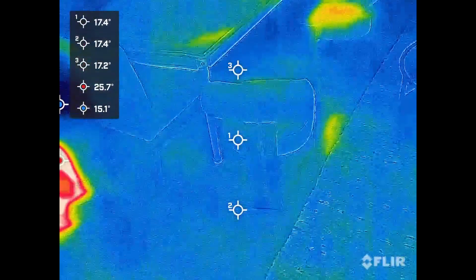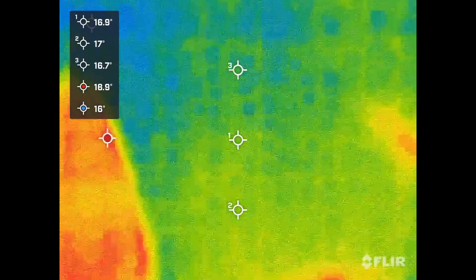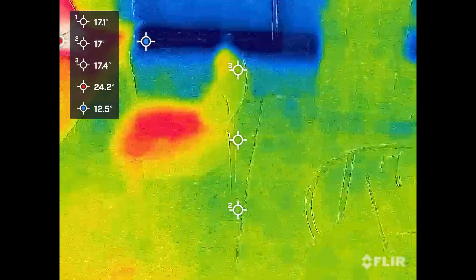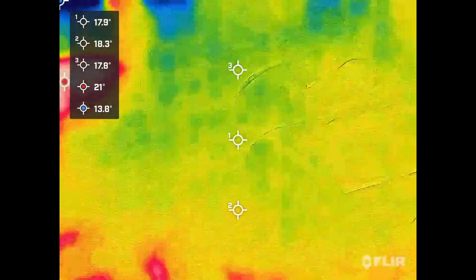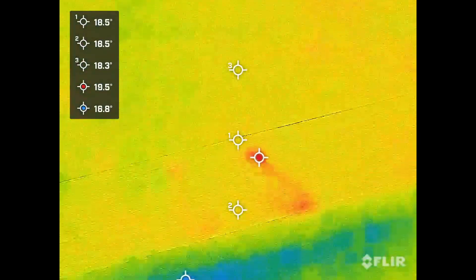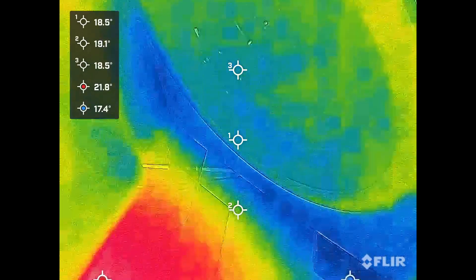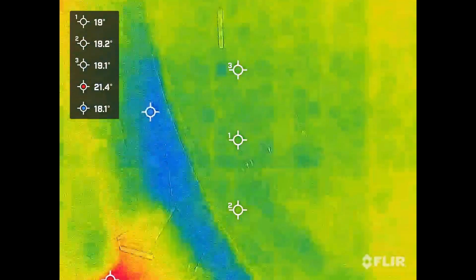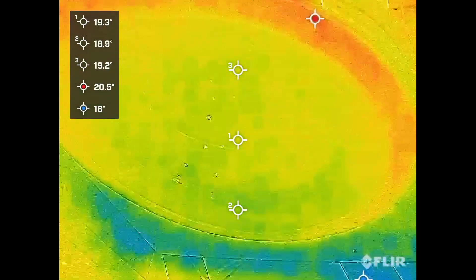The heating is very sporadic — it says it's Wednesday at 8:17, so it's got some very bizarre settings. When there's underfloor heating, you can see it on the thermal imaging camera as loops, but I'm not seeing it now. Do have a look at all the other videos I've put up — it'll make you realise I'm doing this transparently to try and solve people's problems. There's lots of heat loss around here, and you have to remember there's no heat gain in the cupboard. Insulation is really the solution — insulate underneath and around. You've got a cold subfloor void from cold air underneath the timber floor.